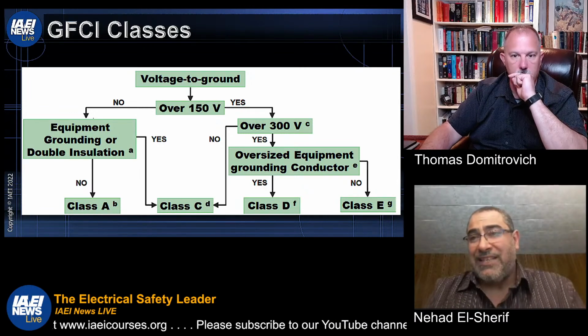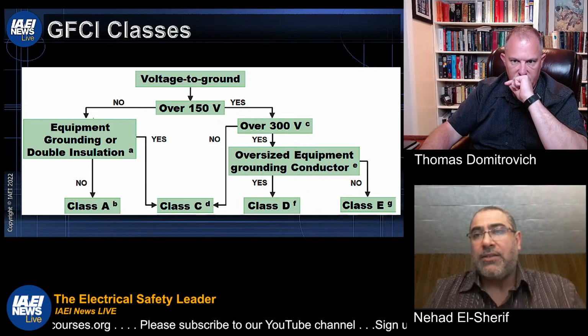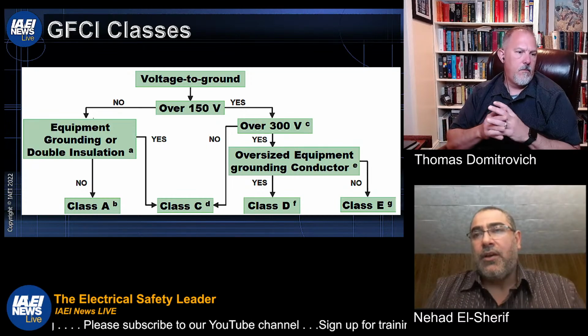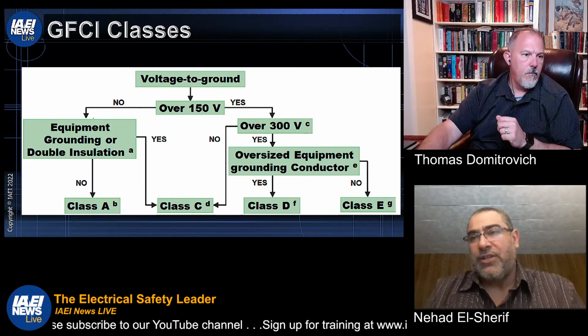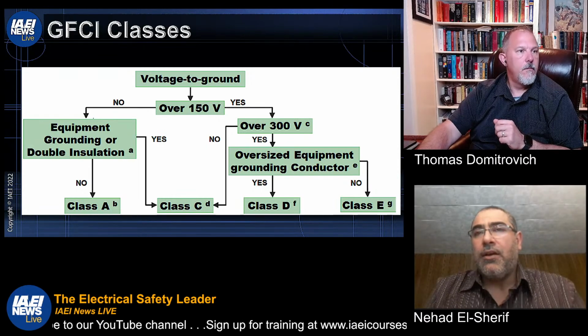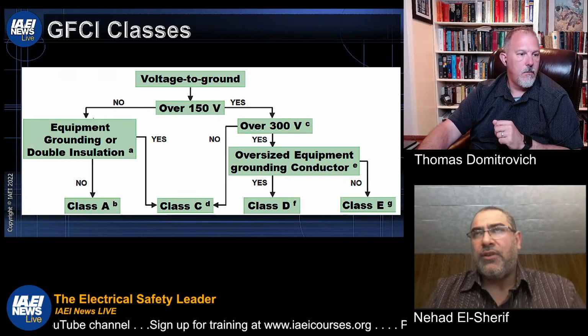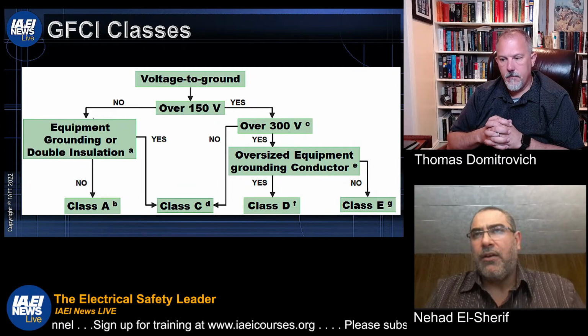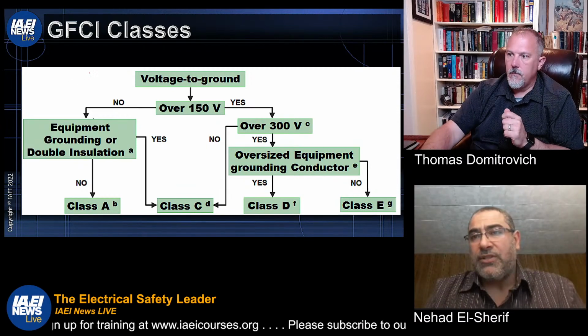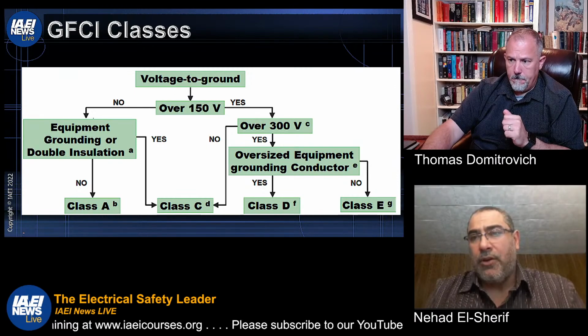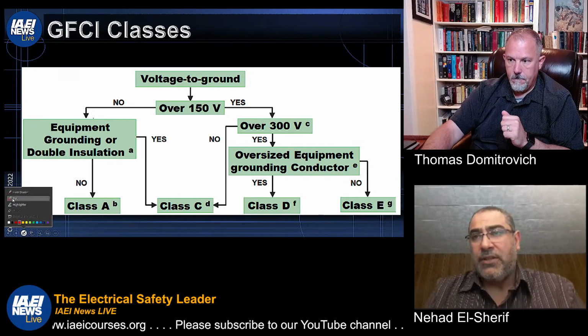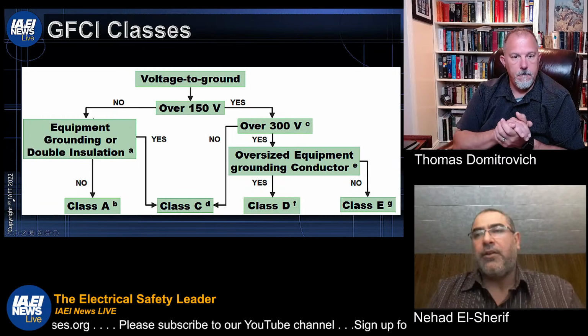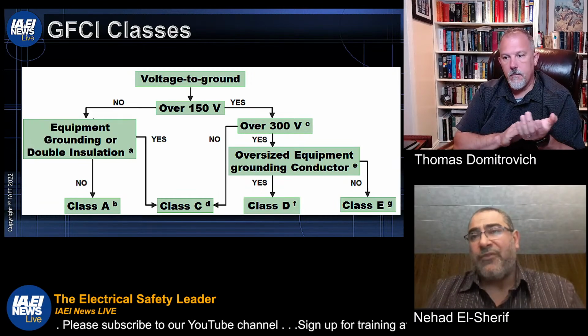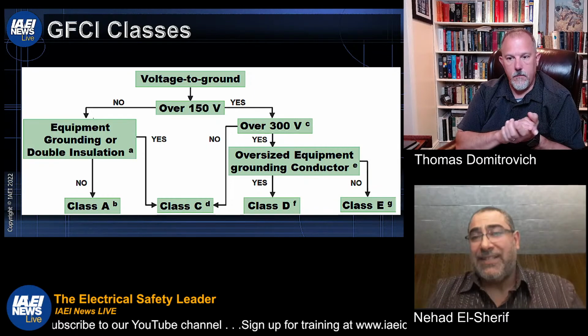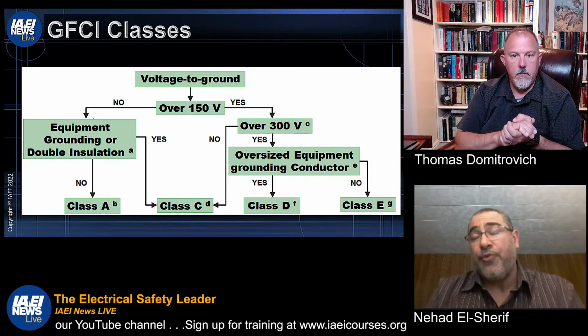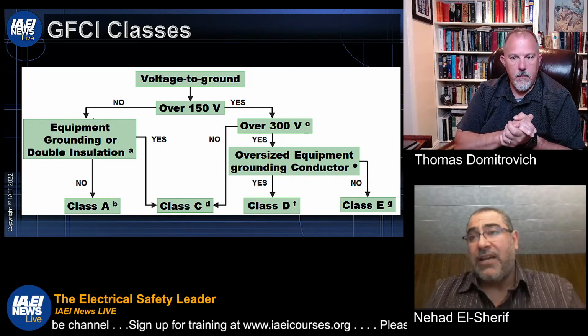The bad news is Class E does not exist as we speak, because of the new equation that Class E has when you go over 250 milliamp. You can't obtain that trip time with a mechanical device, like a breaker or any mechanical contacts, to trip that fast. So Class E, as we speak, does not exist. The only special purpose GFCIs that commercially exist are Class C and Class D.